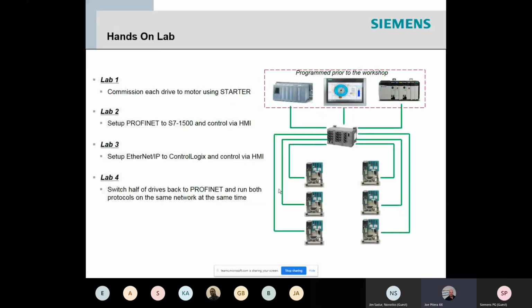In the hands-on lab, we will commission the G120 drive. We will have it talking to the 1500 via the HMI. Then I will flip a bit and plug in the Control Logix and have the HMI talking to the Control Logix, and the Control Logix talking EtherNet/IP to the drive. Since this lab is being run on a webinar and is reduced in time, by showing that the same drive can switch from Profinet to EtherNet/IP, I should be able to prove out that you can run both networks at the same time.